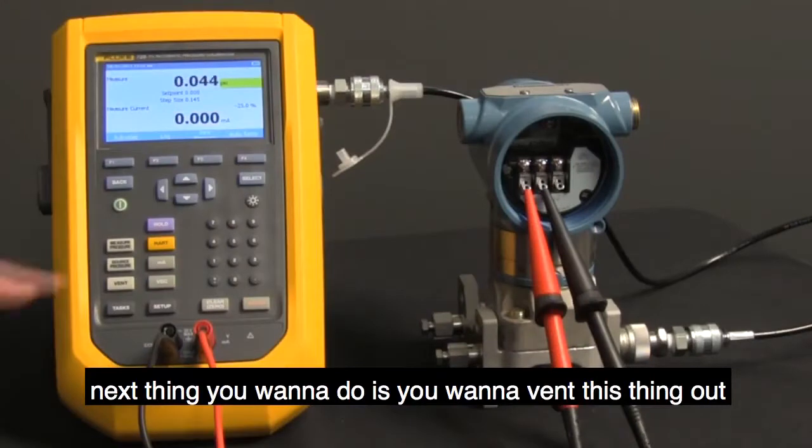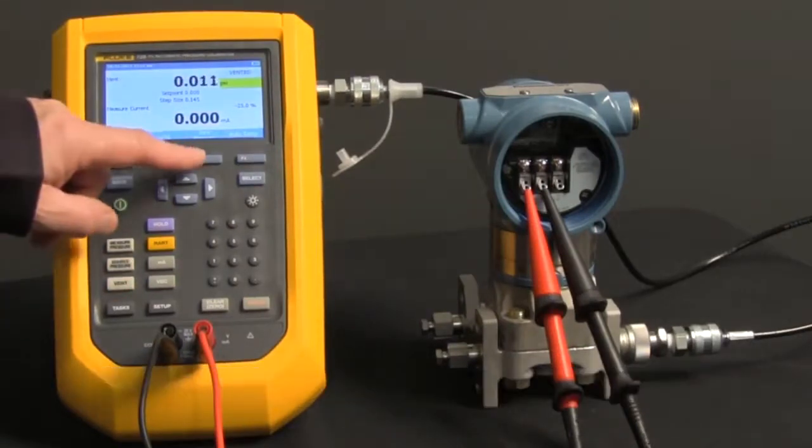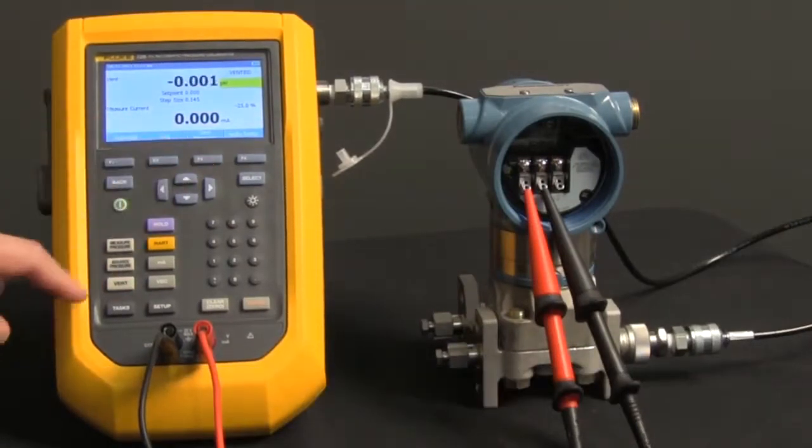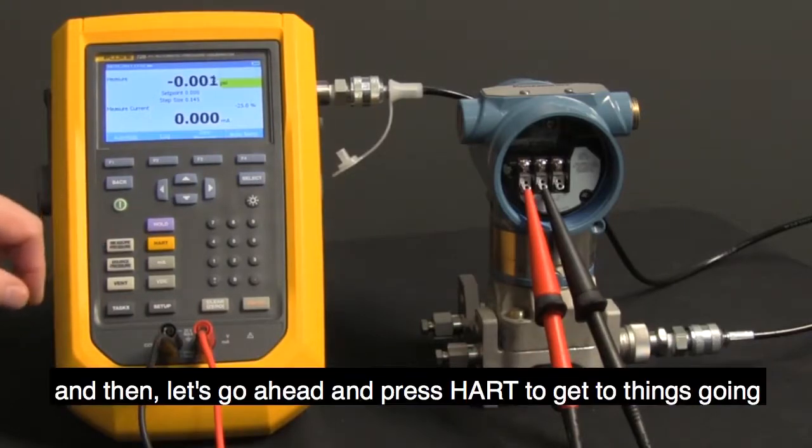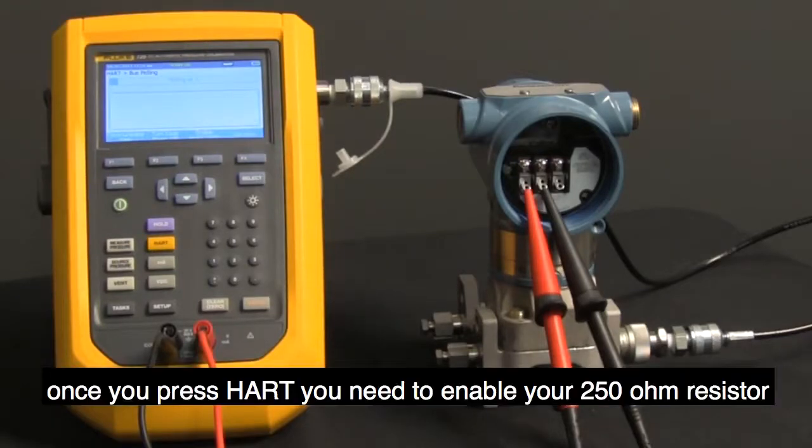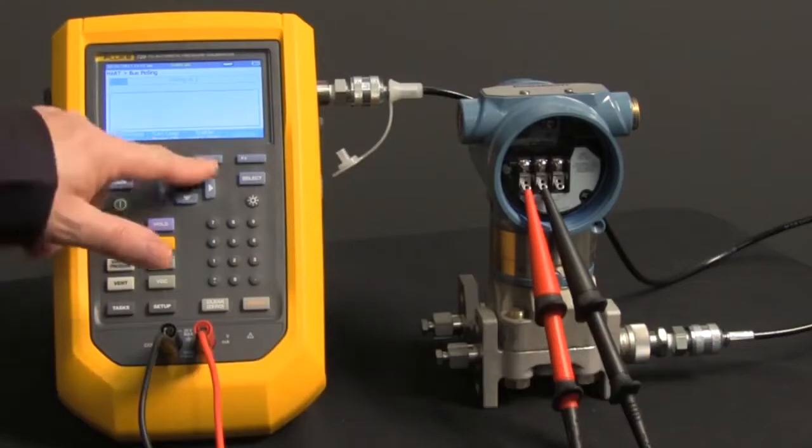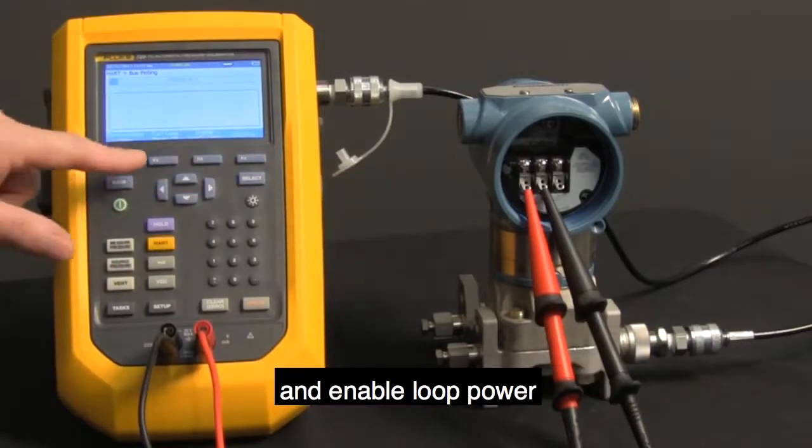Next thing you want to do is vent this thing out, zero your pressure, and then let's go ahead and press HART to get things going. Once you press HART, you need to enable your 250 ohm resistor and enable loop power.